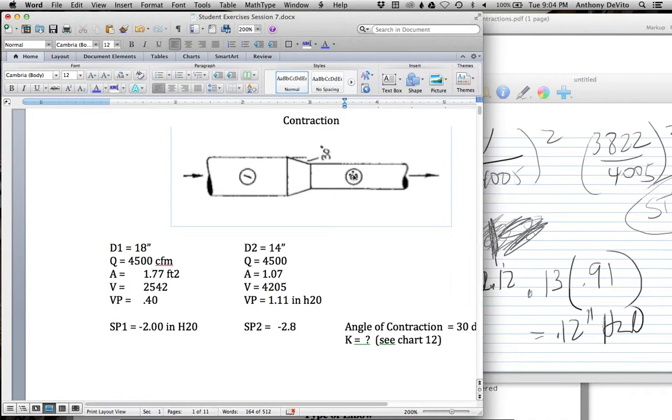What we need here in order to achieve the 2 inches here. It's kind of working backwards, isn't it? In other words, we're figuring out what static pressure we need here to get the 2 inches that we want here. And that's really kind of the way you almost always work, because you're starting at the hood end and you need 1 inch of static pressure at the hood end in order to get the capture velocity you want.